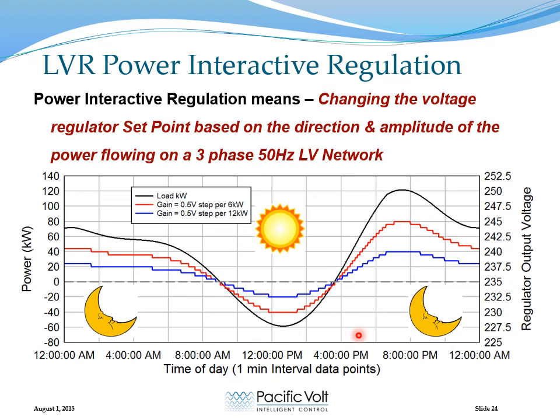In order to manage these issues without spending a lot of money to rebuild the feeder, we developed this feature, and the red and the blue line represent 2 out of an infinite number of options to change the set point as a function of the power flow and direction. In the early morning, when you have normal power flow, we raise the voltage. And as the power flow crosses to 0 and goes into reverse, we lower the voltage out of the regulator, and this counteracts the voltage rise from the reverse power flow on the LV network.